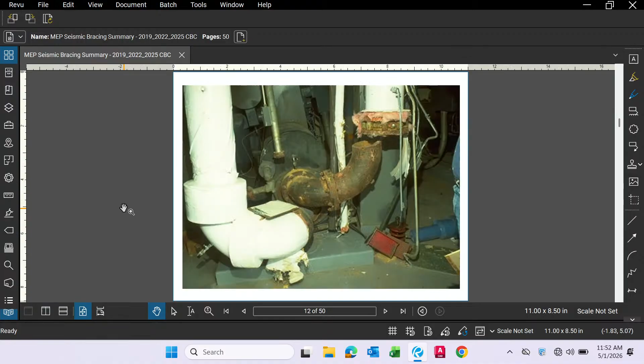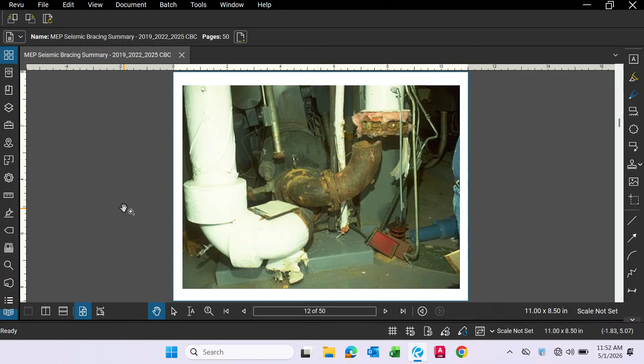And that's exactly what happened during the Northridge quake back in '93 or '94. You can see there the piping doesn't have any flex connectors. At the equipment connection, it just sheared off, because the floor and the ceiling above went in different directions. And even the smallest piece of equipment, such as a fan coil, that type of relative displacement can cause a lot of damage too.